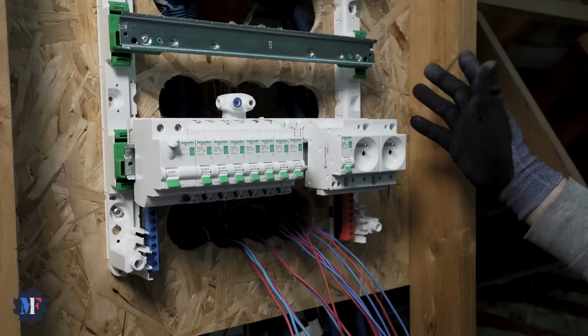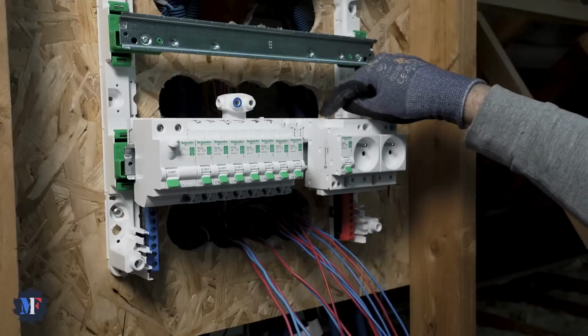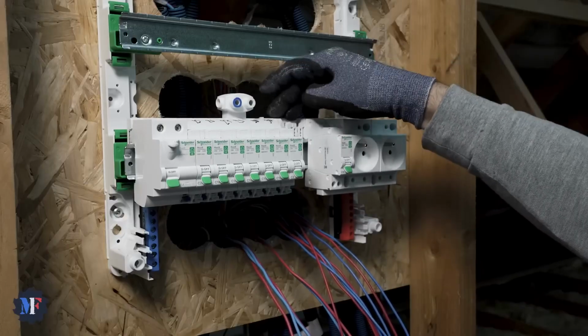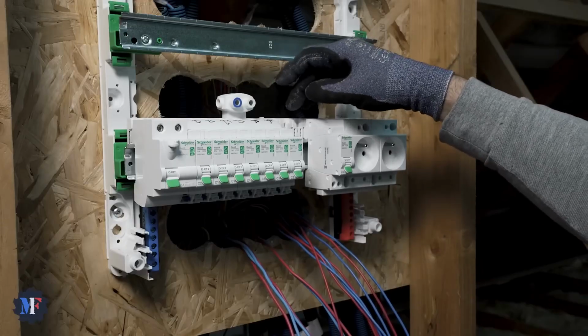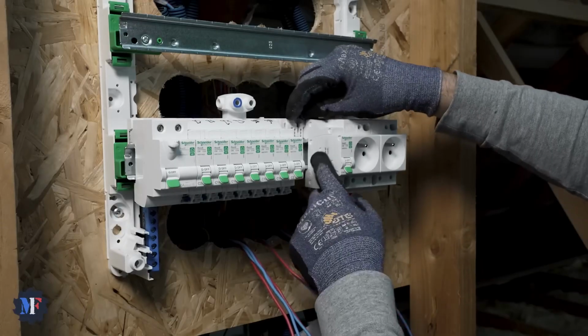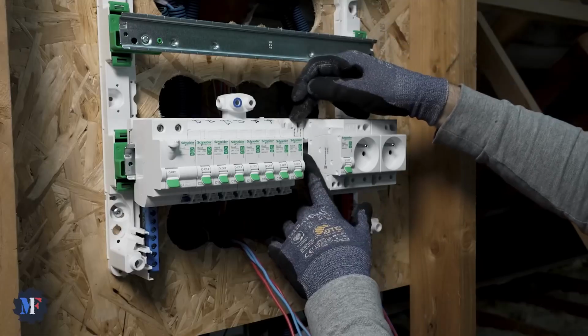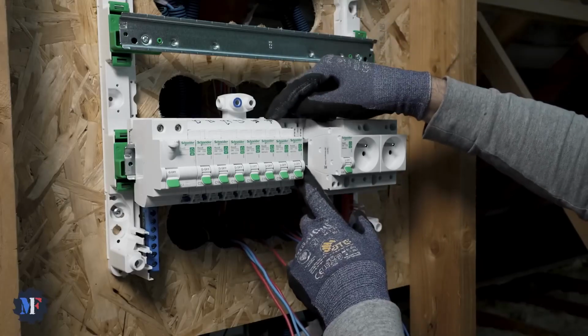We lock it underneath, I don't need to connect it, it's directly powered by the distributor. I have 3 modules left. A remote switch uses 2 modules, a water heater contactor also takes 2 modules, and we'd install a 2A breaker to protect it.